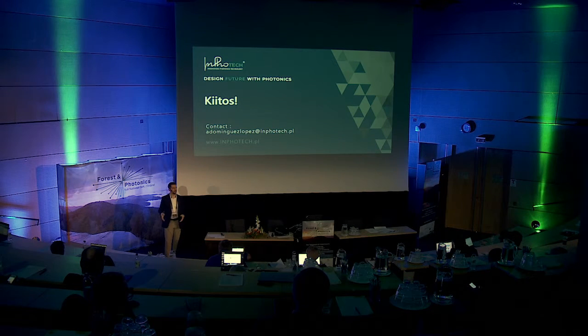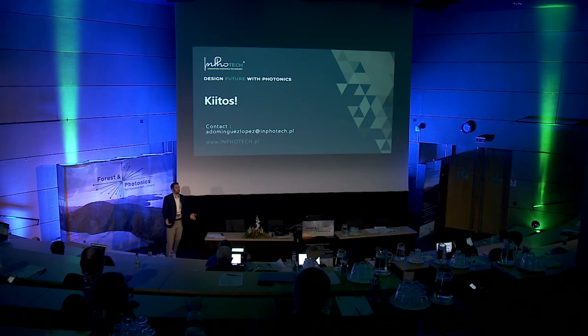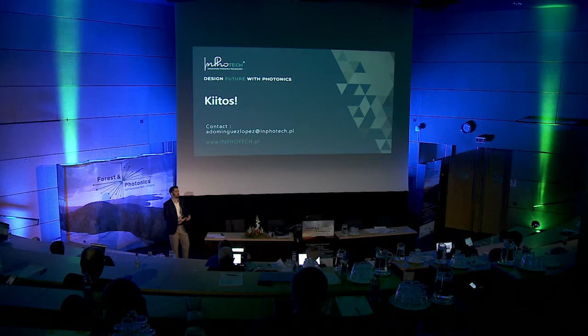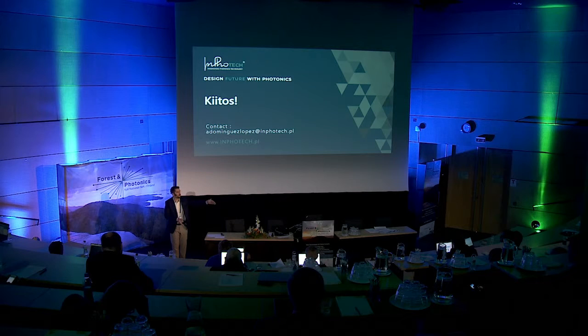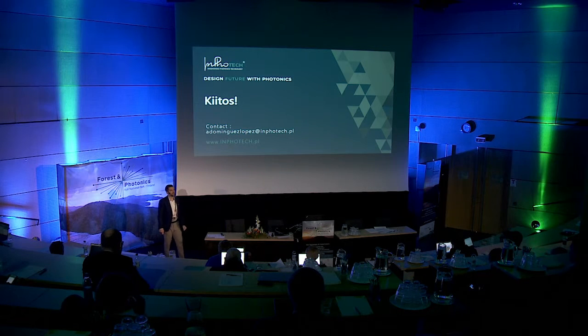That is regarding the perimeter control. But then regarding temperature, it also depends on the dynamics of the material where the fiber is embedded. So if it's in the ground, of course, the temperature dynamic is a bit slower than the pressure waves moving in the soil. But you can detect it tens of meters away from it. Of course, you cannot determine the same at the same time. But if there is a hot spot and the fiber is there, it will reach it at some time and probably degrade the temperature a little bit. But it is quite sensitive.